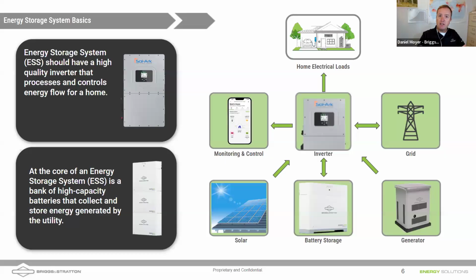As we take a look at this diagram, which we share a lot in our talks - what do we have? Right in the middle is our hybrid inverter. This is where our transfer switch is, where our charge controller is, where the inverter and battery charger is. And this is also where a lot of the controls are for time-of-use control and potential peak demand shaving, and where we bring in the generator.